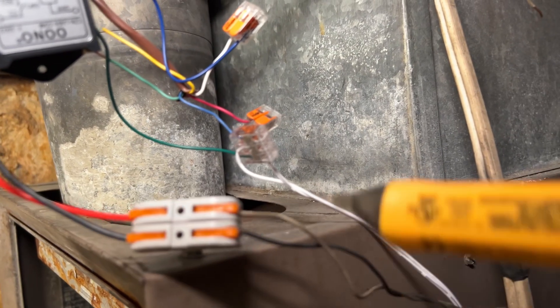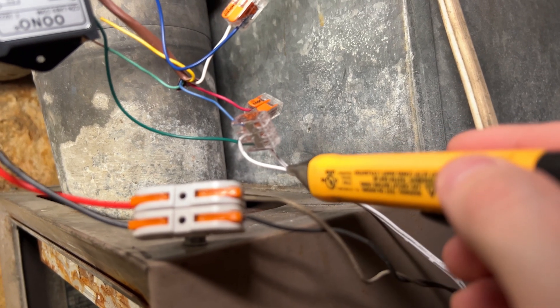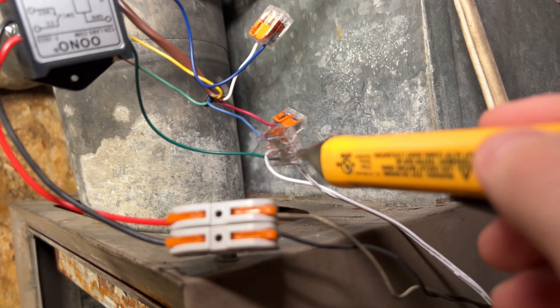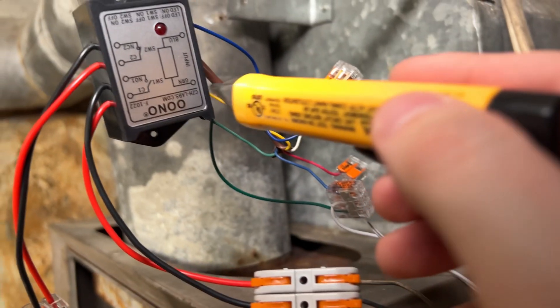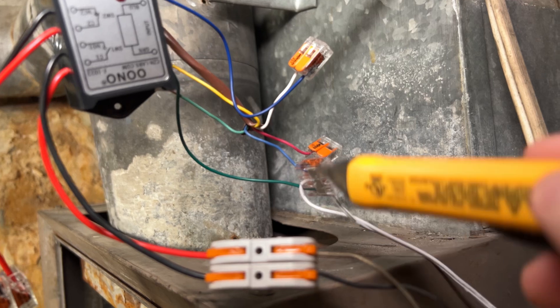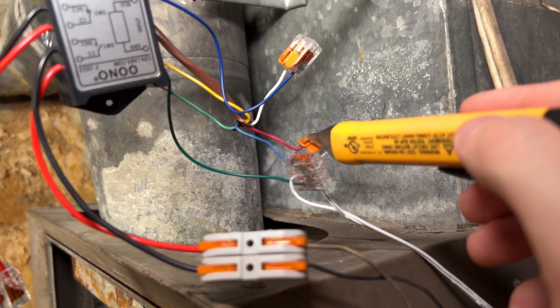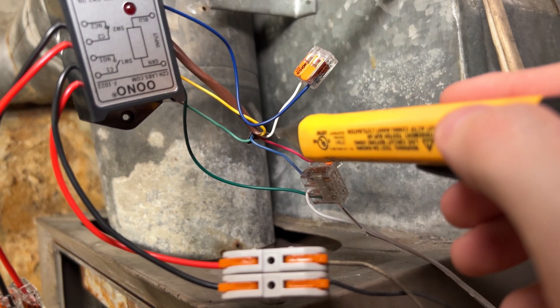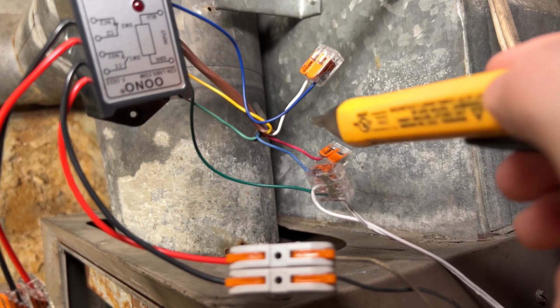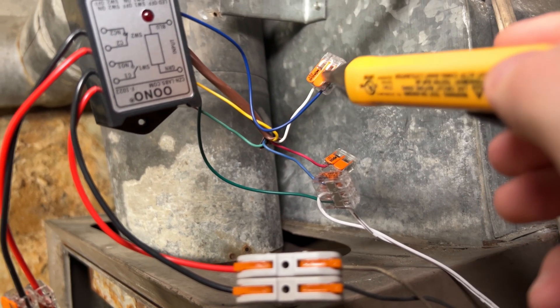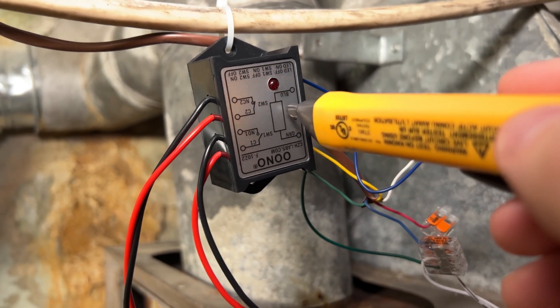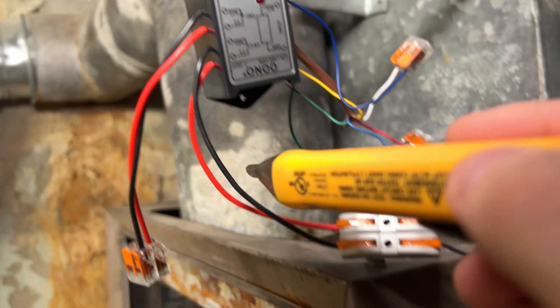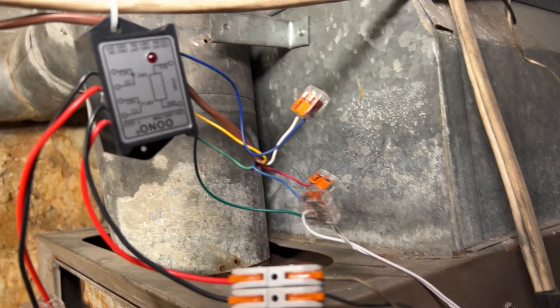So just really quickly again to recap: here's our incoming power wire, this white wire. Doesn't matter which one, one of them is split with this Wago, half of it goes to one side of the relay, half of it goes to common, the other side goes to our red wire, our 24 volt R wire. When the thermostat calls for heat, it sends 24 volts from here back on to the white wire, which we connect to the other side of the relay. When the relay gets power, it closes this switch, which connects the white and black, which turns our furnace on.